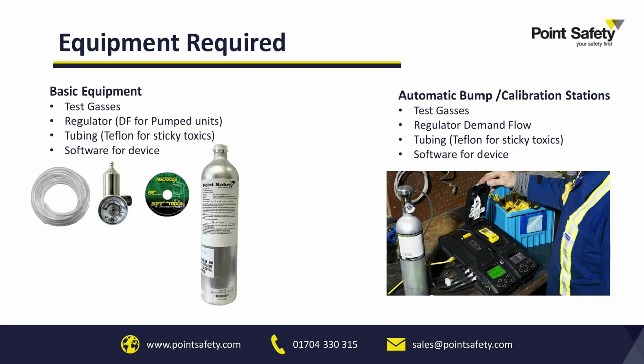Using a demand flow regulator, it will draw the gas from your mixture into the docking station. It'll apply that to the meter. It will carry out all the calibration adjustments that are needed, and then it will tell you whether it's passed or failed. Normally, if it's failed, it'll be a blocked sensor, a blocked filter, or the sensor is no longer working beyond its economical life. That will also transmit to the relevant software of the dock that you're using, again creating your records of calibration. Possibly other items, including asset management, might be included in that.